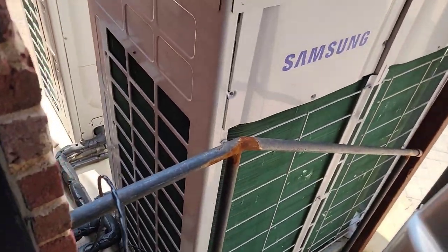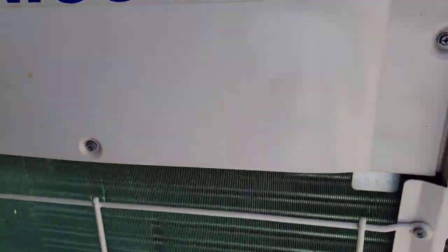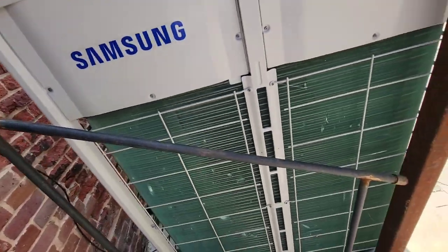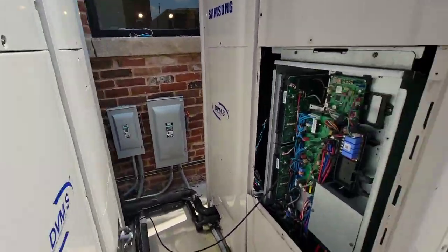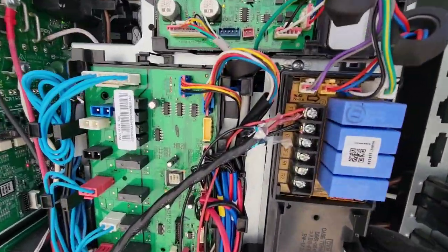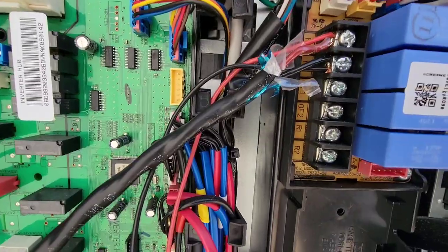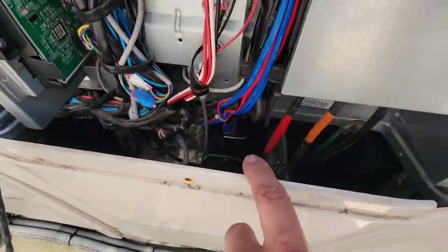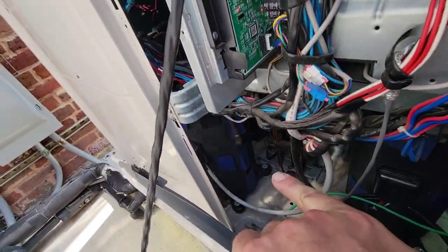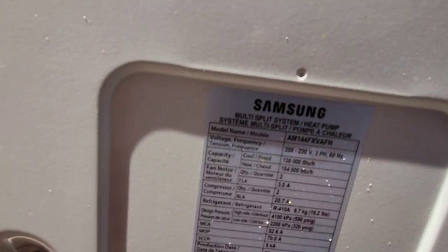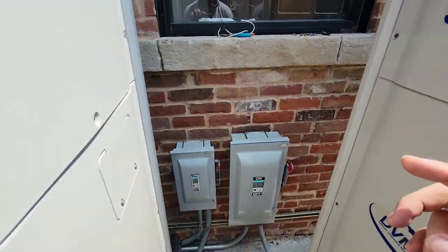That goes outdoors to my F1 and F2. We've got the yellow light. We've also got the green light. That is key. See the little green blinking? This right here is where I hooked up my wires. F1 and F2. There's one compressor down here. BLDC three phase scroll. There's another compressor right there. I love these units. And this one is a 12 ton. See that model and serial number. So we got a 12 ton and a 10 ton. And I love S net because doing a startup.